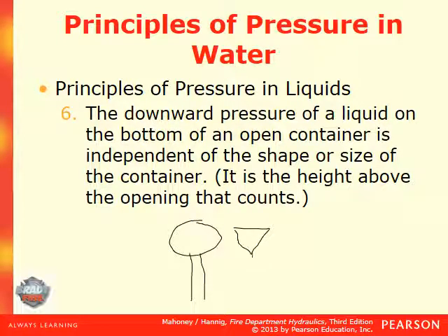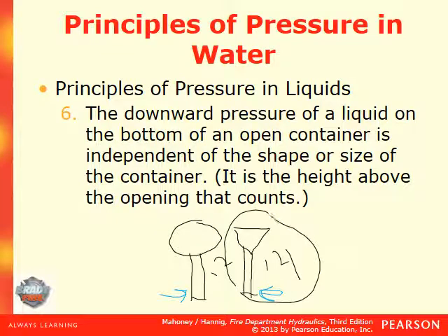No matter the size or the shape of the top, the pressure at the bottom here will be the same if they're both the same height. However, if we have this one 14 feet high and this one 12 feet high, the 14 foot high will exert more pressure at the base.